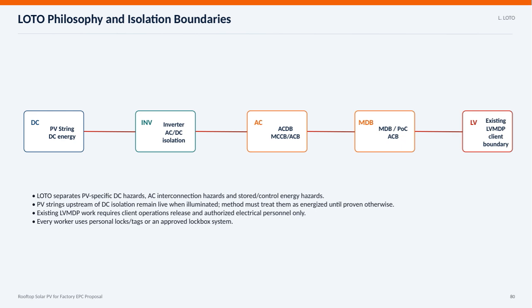Also, any work on the existing low-voltage main distribution panel requires a formal release from client operations and must be handled by authorized electrical personnel only. To ensure safety, every worker applies their personal locks and tags or uses an approved lockbox system, so nobody can accidentally re-energize the system while work is ongoing.